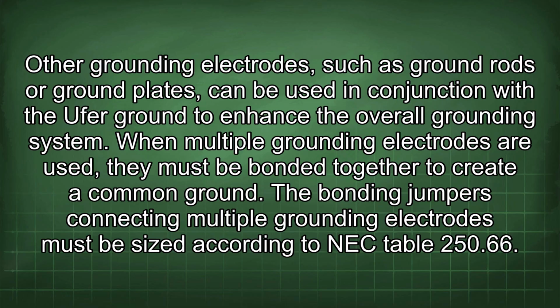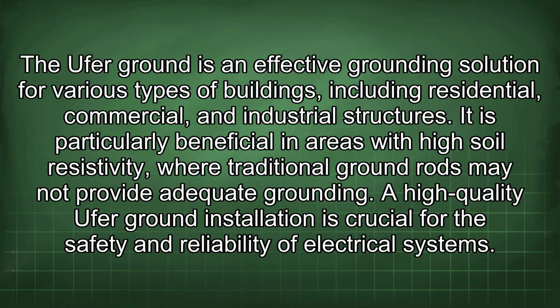When multiple grounding electrodes are used, they must be bonded together to create a common ground. The bonding jumpers connecting multiple grounding electrodes must be sized according to NEC Table 250.66. The Ufer ground is an effective grounding solution for various types of buildings, including residential, commercial, and industrial structures. It is particularly beneficial in areas with high soil resistivity where traditional ground rods may not provide adequate grounding.